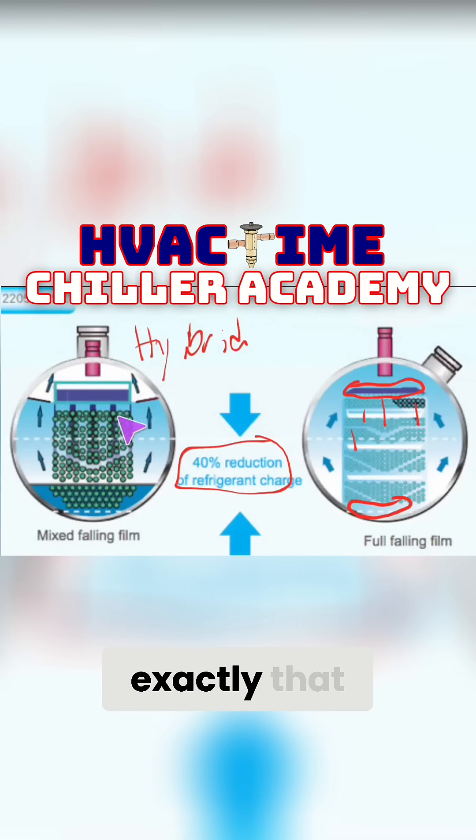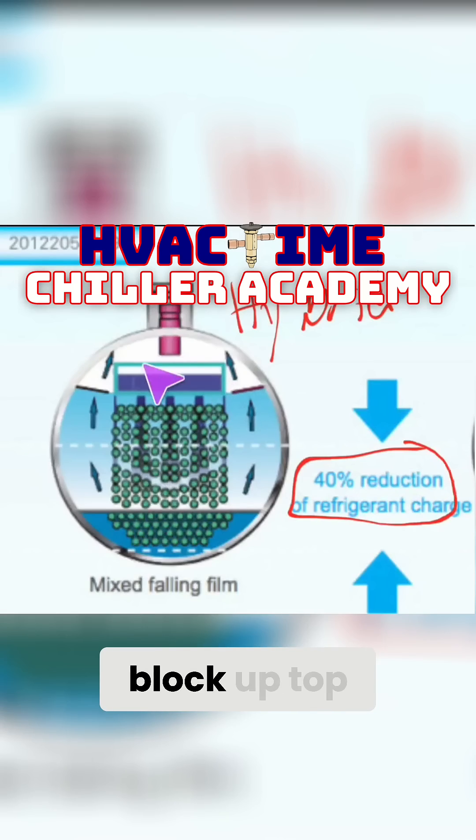The hybrid evaporator is exactly that. The goal is we're still using the concept of the falling film, having refrigerant rain down and just boil off as it goes and gets collected back into the suction. It has a distribution block up top. Liquid refrigerant is injected into the top of it and goes through a metering device.